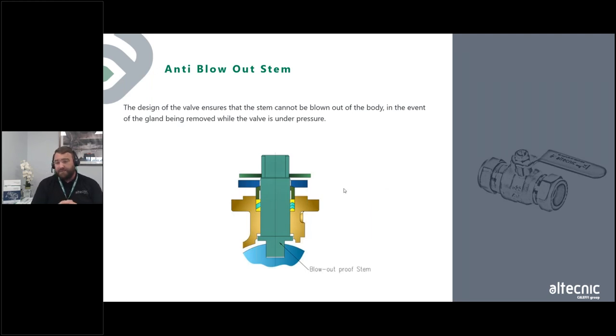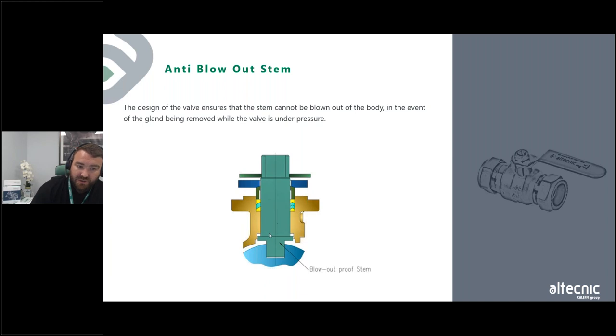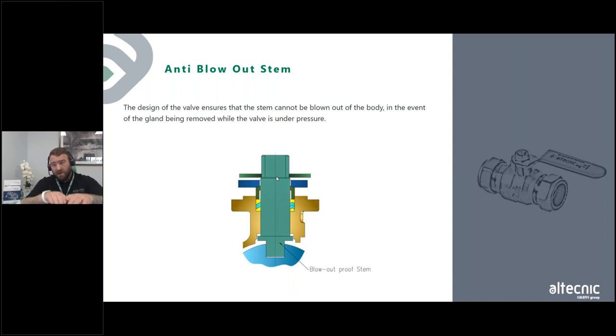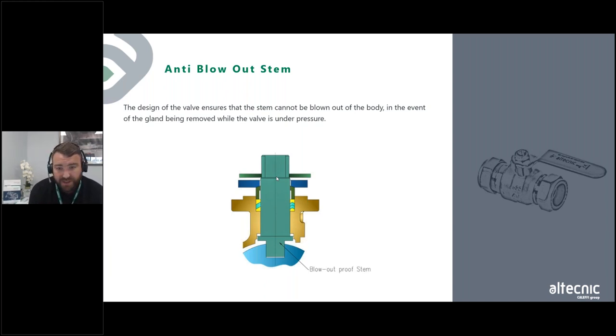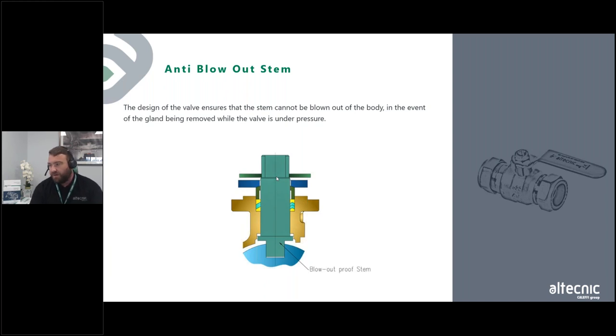The anti-blow-out stem is a very important part of the valve. The design ensures that the stem cannot be blown out of the body in the event of the gland being removed or the valve being under pressure. Before the ball is fitted in the body, the stem is pushed through from the inside with a lip on the bottom, so it cannot be pulled all the way through. Even if the glands are removed, it stops it from coming out. Always look for this anti-blow-out stem feature — it prevents serious problems from deterioration or accidental gland removal.